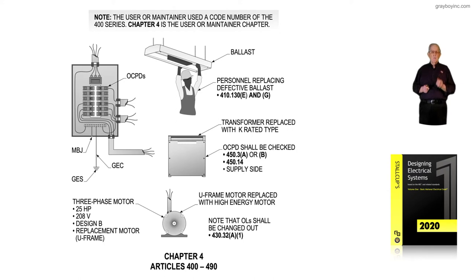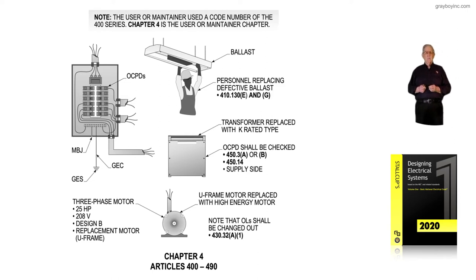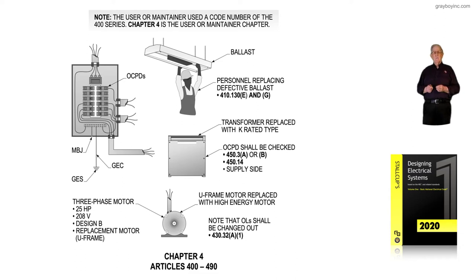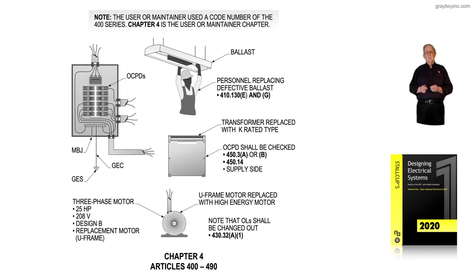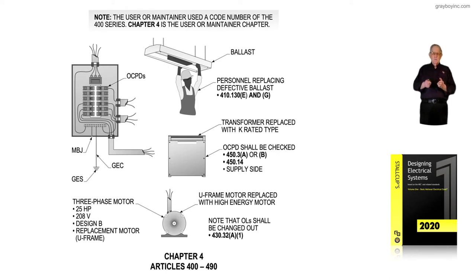Notice we have a three-phase motor that we've already designed everything for — it's 25-horse, 208-volt, Design B. If we were replacing that motor, and it was an old U-frame being replaced with a T-frame, we'd have to go to Article 430 to perform such a task. Notice that the overloads would usually have to be changed out in accordance with 430.32A1, sizing overloads at the minimum value to protect the motor, but you could drop the overload down if it did the job.